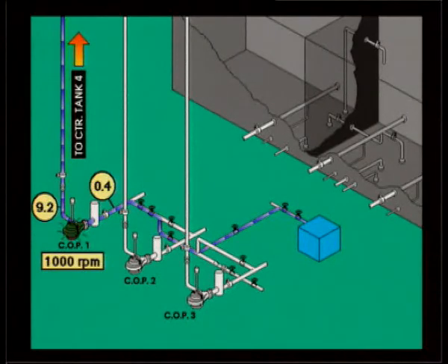In our vessel, the speed of the pumps will be approximately 1,000 revolutions while ballasting. There is no point running a pump at full speed if you can reach a high capacity running the pump slower. Remember, this way you will save fuel and money. In this case, you're adjusting the speed and the pressures to get a head of 86 meters.